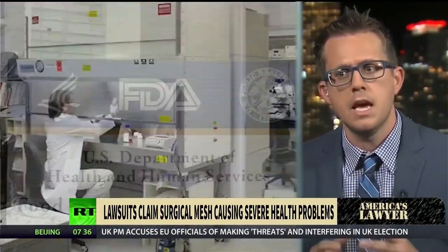Yes, so the FDA, many people don't know this. Even sometimes doctors, when we talk to them, don't know this. But the FDA, if you have a medical device, and it's not what we call a life-sustaining device like a pacemaker or something like that, you can present it to the FDA, and instead of studying the device for safety and efficacy, all you have to do is say, okay, FDA, I've got this mesh, and it is what we call substantially similar to another mesh that's on the market. I'm just like these other guys, approve me. And that's called fast tracking through the 510K process.